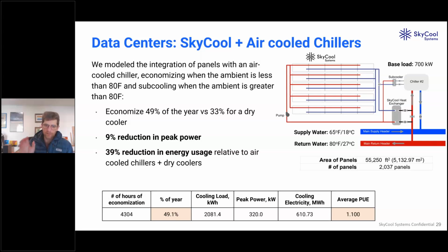But the difference between, say, using our panels and a dry cooler is we were able to add about 15% more hours out of the year where we could economize the system. And that's really driven by the fact that the panels have a much lower approach to the ambient. When you have a fan, you need to have a fluid that is above the ambient. And essentially with these panels, we can cool fluid up to the ambient or even below the ambient. And so there's just more hours where we can economize in the year.